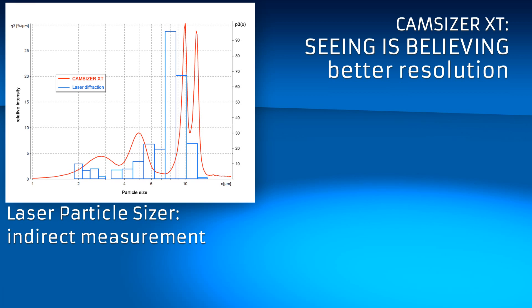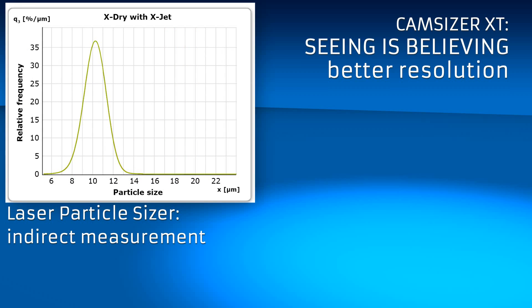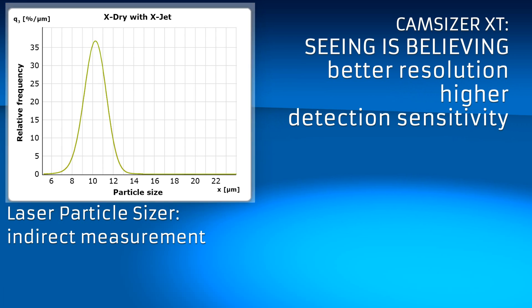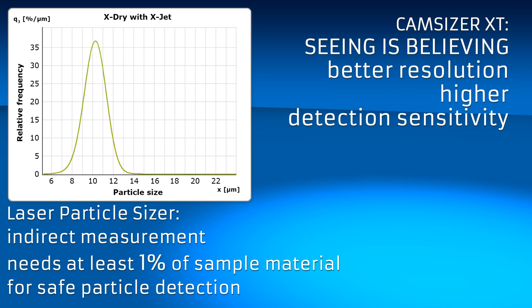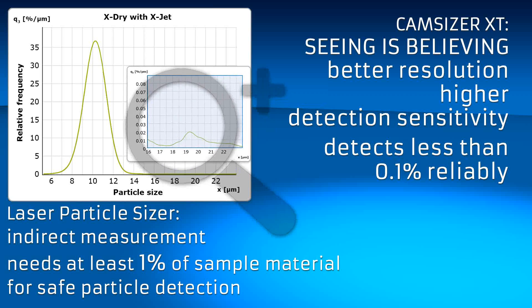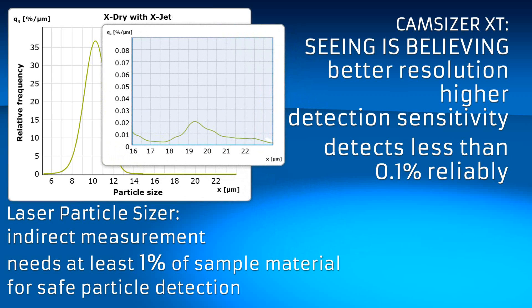The CamSizer XT not only offers better resolution, it also features a higher detection sensitivity. Whereas a typical laser diffraction analyzer needs at least 1% of material for the safe detection of oversized or undersized particles, the CamSizer XT can already detect less than 0.1% reliably.